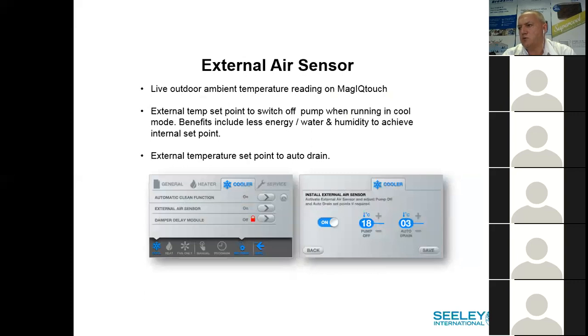External temperature set point to switch off pump when running in cool mode, and then external temperature set point to auto drain. Let me explain those to you. The external temperature set point. So as an example, let's say that you set your internal temperature to be 23 degrees. But your outside temperature actually gets to 23 degrees. What's the point of having extra cooling? As an example, you don't need the extra cooling, just keep it at 23 degrees. So it'll switch the pump off, saving water, saving power, of course, and therefore a benefit to the customer.